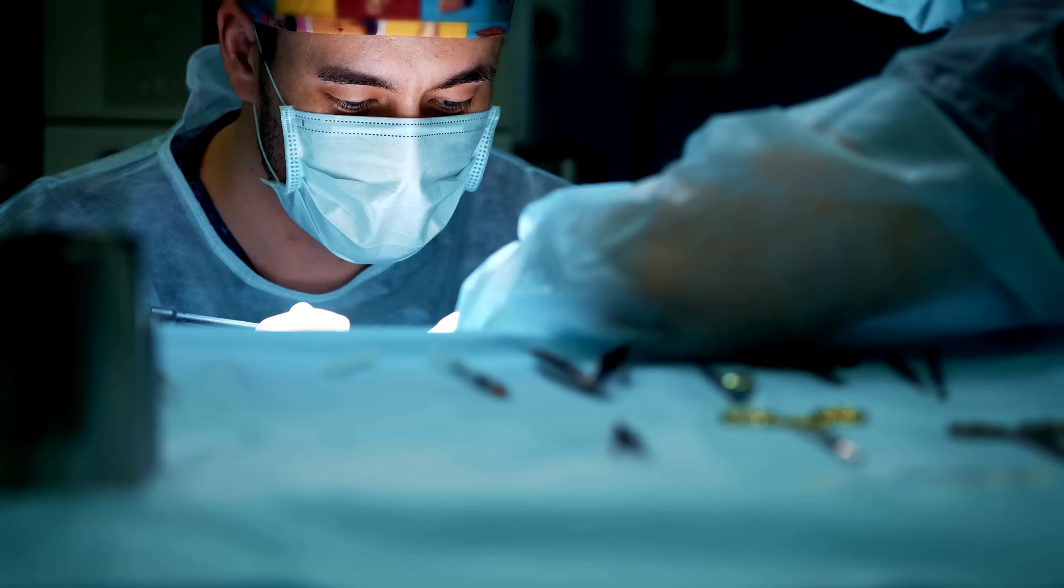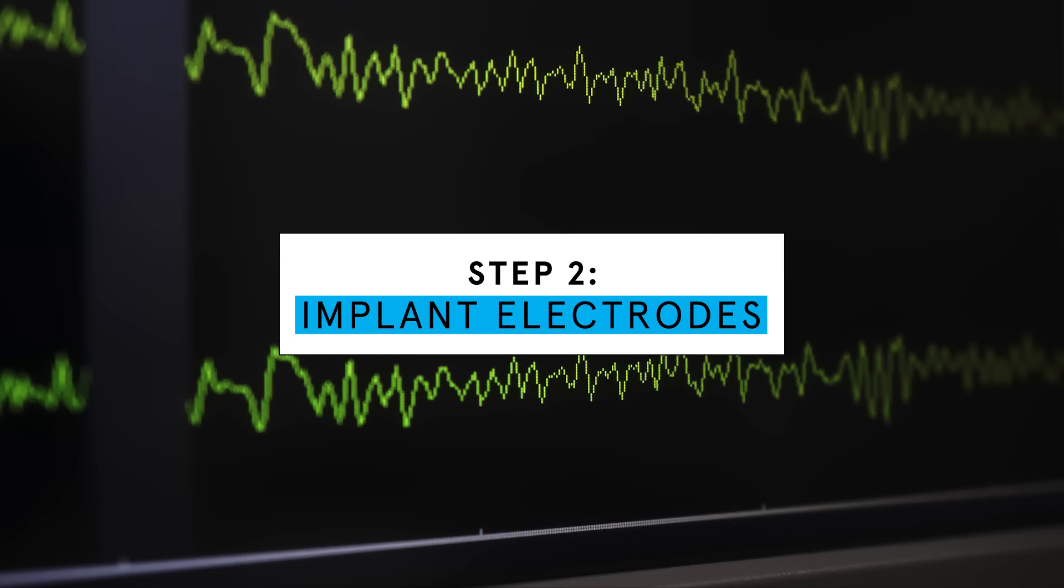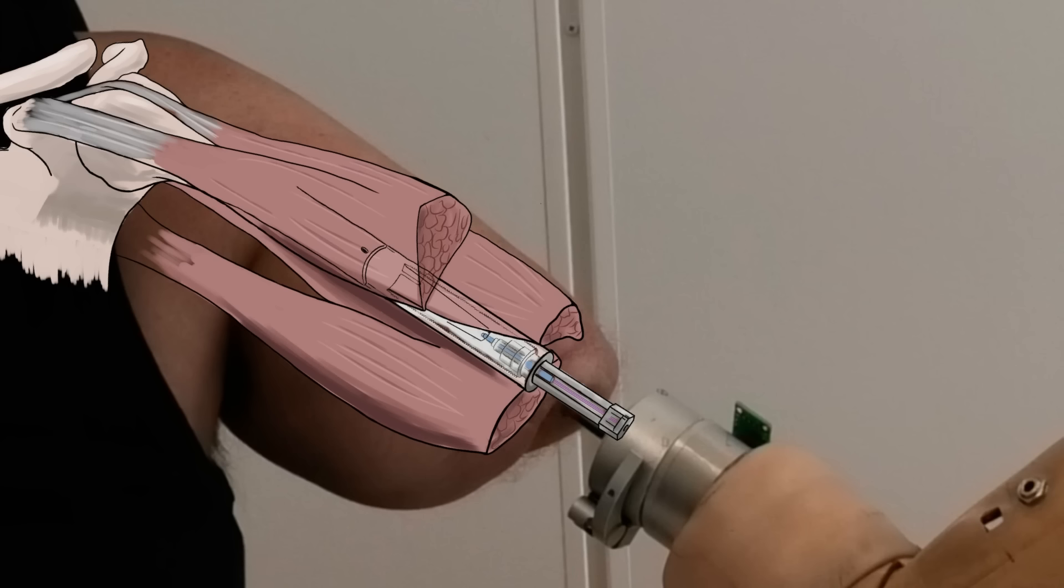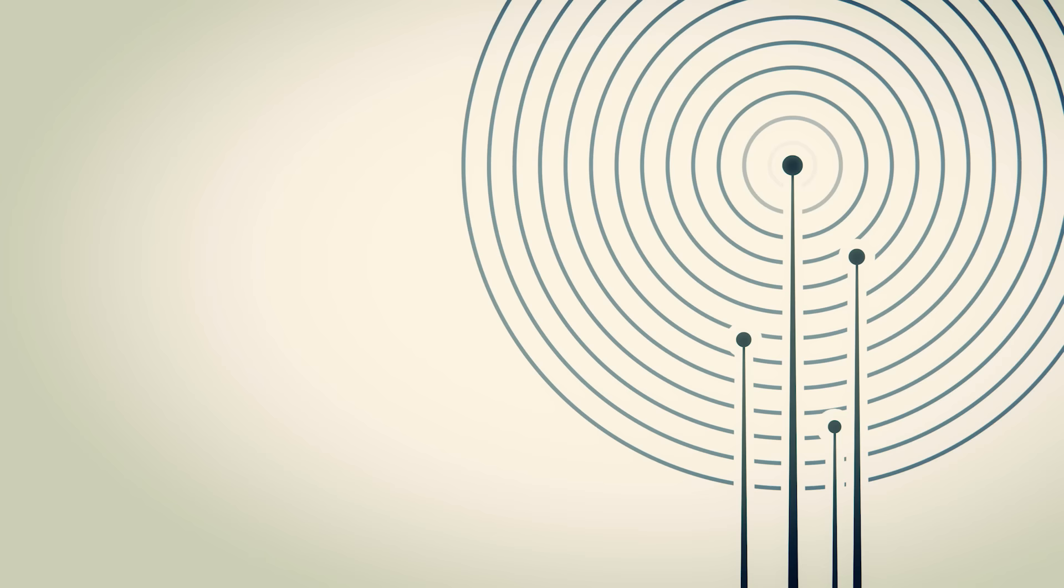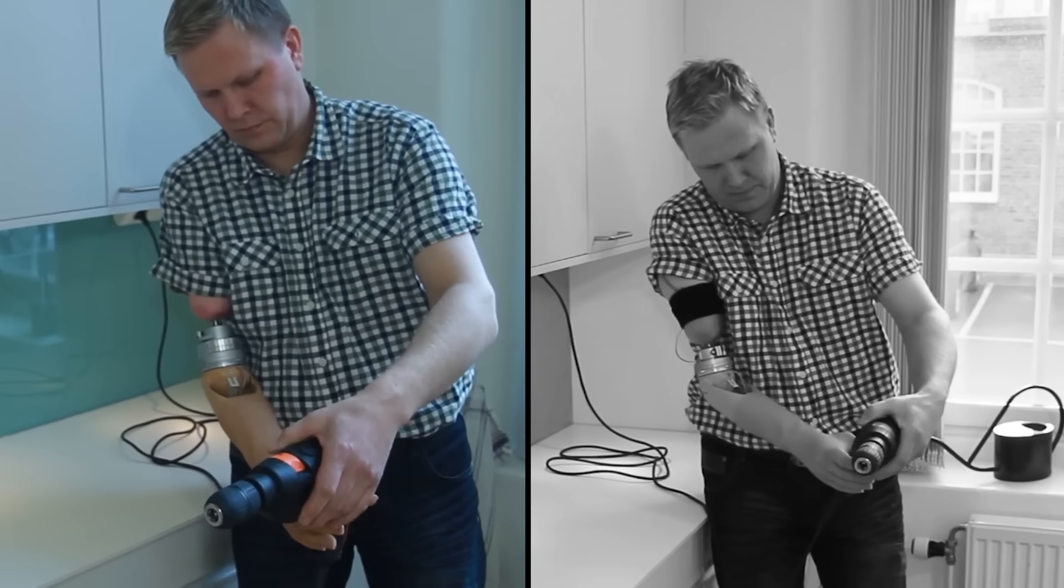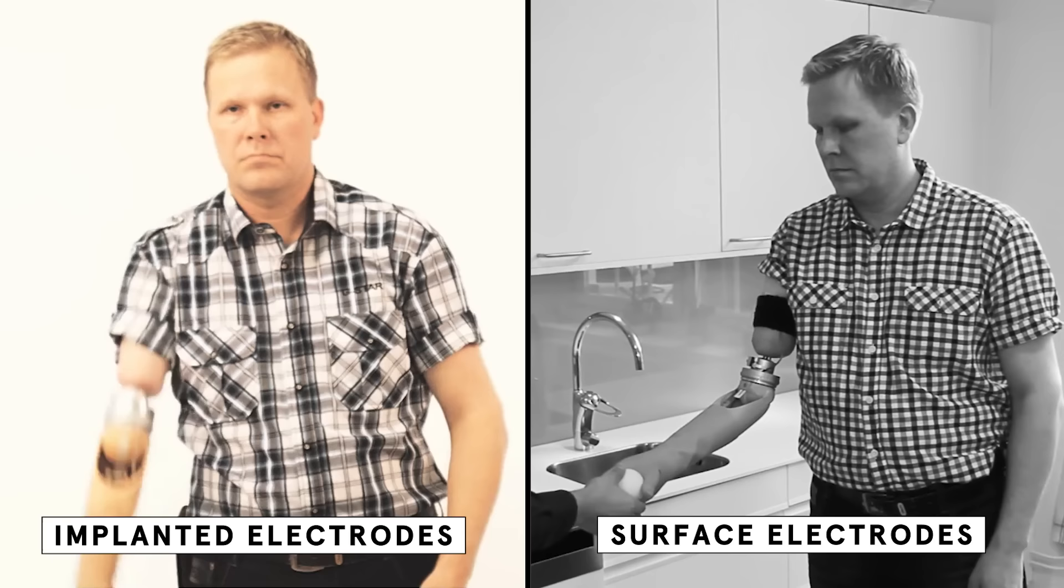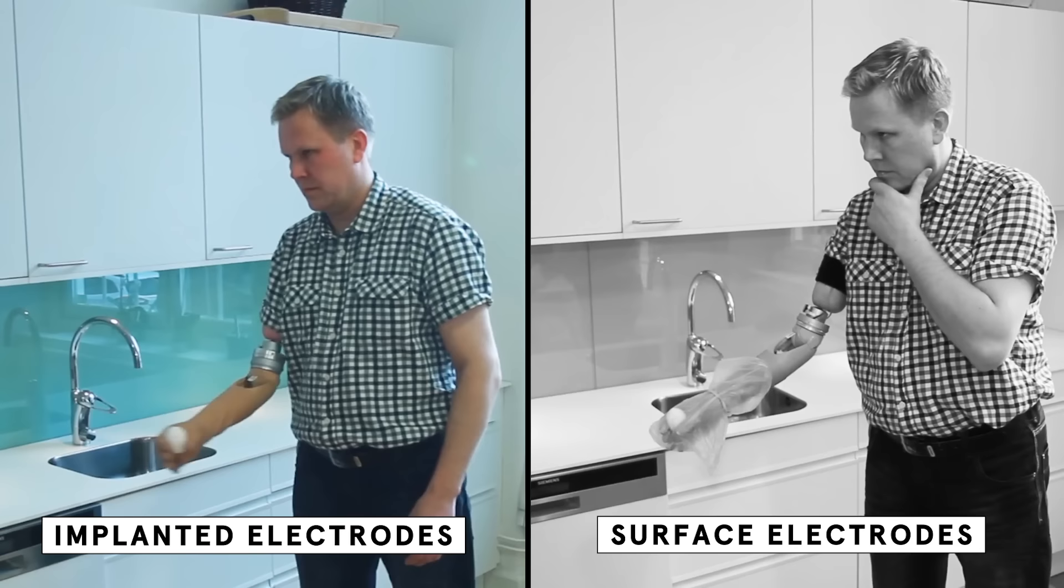Now, the next step is to surgically implant the electrodes inside the body. We will place electrodes in the muscles and the nerves around the residual limb. Electrodes on the surface of the skin are susceptible to electromagnetic interference. Stuff all around us, like tools or computers, can create noise interference radiating to the electrodes if they're merely sitting on the surface of the skin. This will cause the prosthetic to become uncontrollable. Even just moving your arm around can throw off a conventional sensor. If it lifts a little bit, it generates this, what's called a motion artifact.